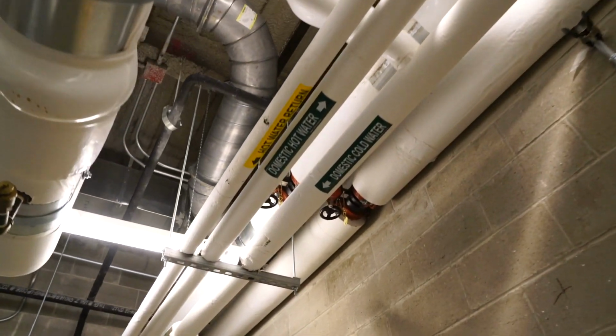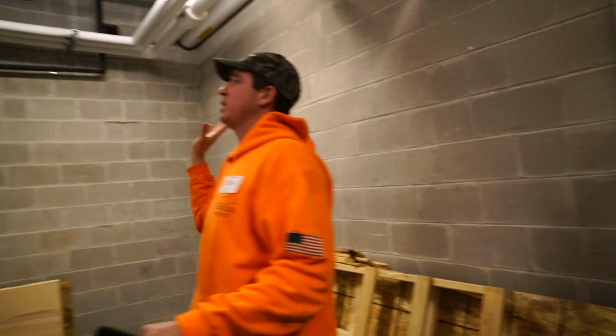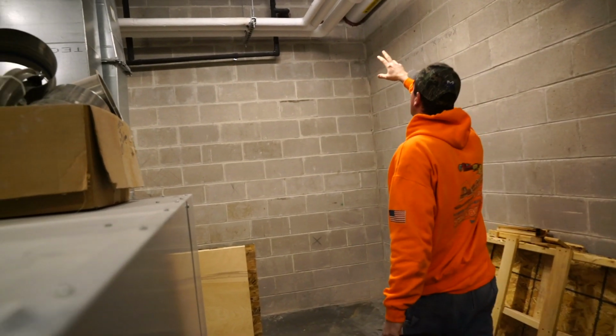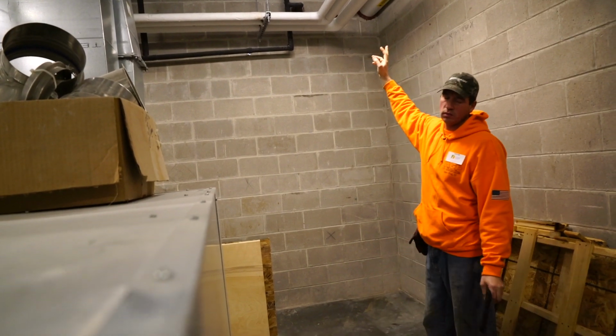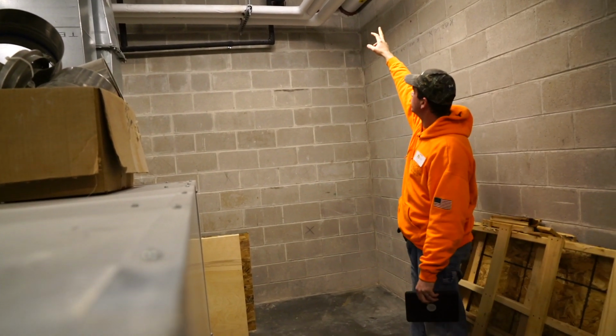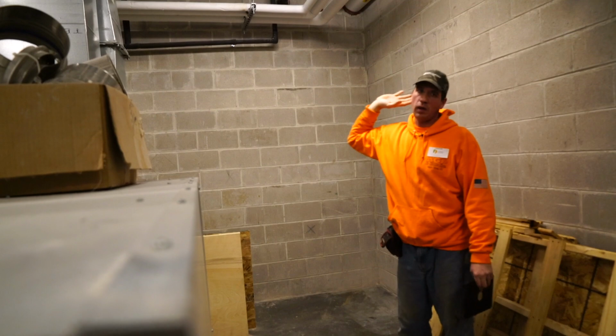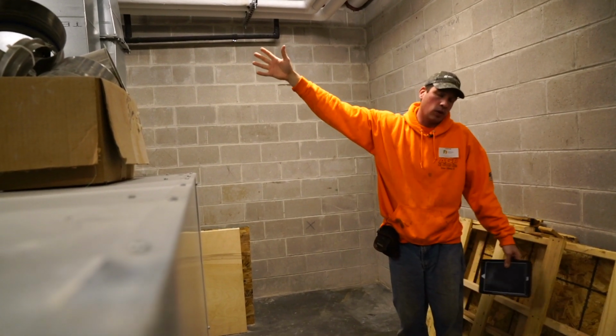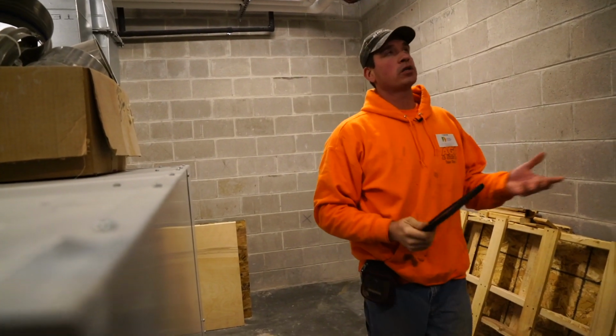These are my 3 plumbing lines, domestic. Cold, hot, return, that's where they go through the wall. Basically, this half of the building you can shut off. I put a separate isolation valve. It wasn't called for, I just put it for testing. So you can shut off the cold right here. It'll isolate that side of the building if you want, for whatever reason. I just put that in there for when I was testing. I needed an extra valve in there.